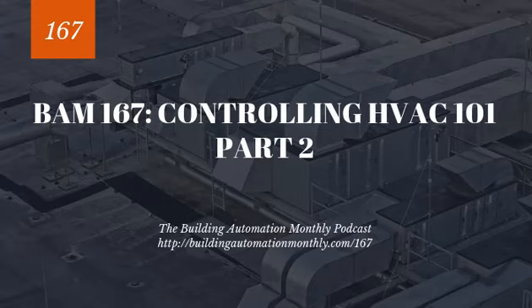So for our safeties in that case, let's say that this mixed air unit is constant volume, we could still have pressure safeties. We could have a damper interlock. We could have a low temp alarm. We could have smoke alarms. All these safeties would have to be true. And then our mixed air dampers, we want to make sure they're controlled. We don't want our outdoor air and our return air damper both being closed at the same time. The air's going to have nowhere to go. The fans are going to start pulling the ductwork in. It's just going to be all kinds of bad.